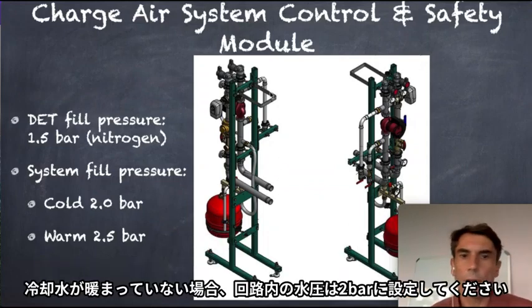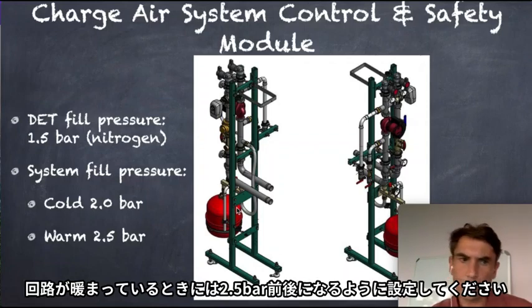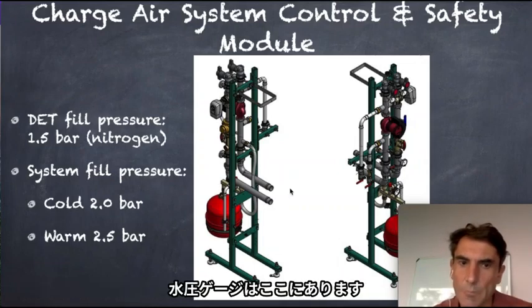Okay, and the water system, the cycle system, must be filled with a water pressure of 2 bar if the cycle or the water is cold. If the water is warm or hot, then the pressure should be around 2.5 bar, and we can again see it here on the pressure gauge. Yeah, here is the pressure gauge.